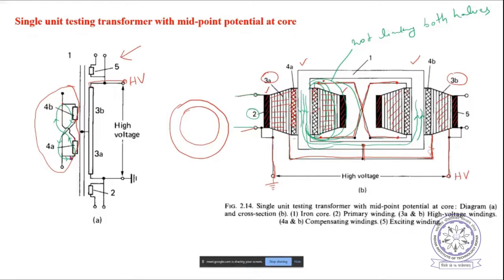That is secondary. They will produce flux which will make the 3A and 3B voltage equal - it will produce flux such that the flux linked to winding 3A and the flux linked to winding 3B are exactly equal. That is the main purpose. Indirectly, you are equating the voltages of 4A and 4B by connecting them in parallel, so whatever flux is linking should be the same for 3A and 3B also, because the voltages are same.